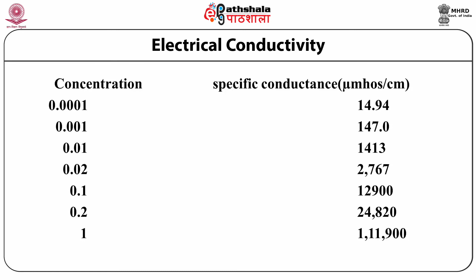Keep the electrode immersed in distilled water so that its functionality is maintained. The electrodes have to be immersed always in distilled water to maintain the conductivity between the electrodes, and the result is expressed as millisiemens per meter or microsiemens per centimeter at a temperature of 25 degrees centigrade.